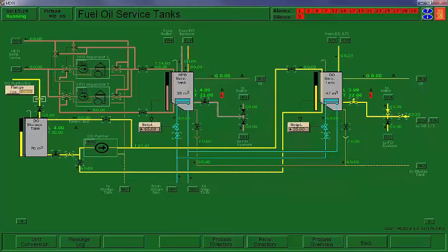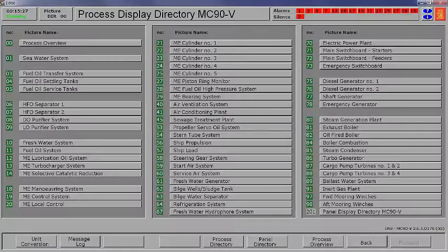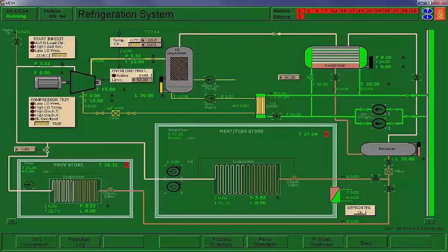Now, the next thing we're going to do is go to that refrigeration system, and it's fairly simple to put on. All right. First thing I'm going to do is this is the vent. This vents the main condenser down to the receiver. And then this is the drop, the liquid from the condenser going down to the receiver. Both of those have to be open. We're going to open up the salt water cooling water line to the lube oil cooler, and also that goes to the condenser, and start a salt water pump.